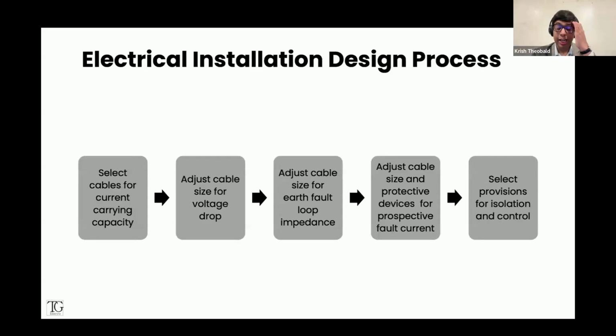When we select cables, there are four things that we generally look at. Number one, we have current carrying capacity. So obviously, how much current can the cable carry in normal operating conditions? Voltage drop. Is the arrangement able to provide an adequate voltage to connected equipment, the voltage that the equipment actually requires to function? Most installations have the protective measure of automatic disconnection of supply for protection against electrical shock. And as we all know, the key thing there is earth fault loop impedance. We have a supply earth fault loop impedance, but the value of earth fault loop impedance and the contribution of fault current at the extremity determines whether the device will disconnect or not. So we need to adjust the cable size to ensure adequate earth fault loop impedance is present.